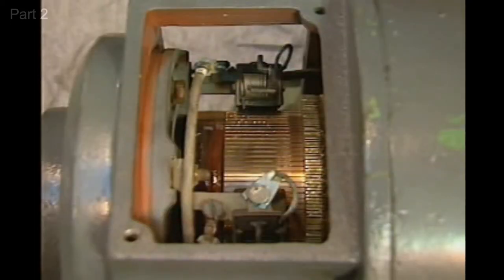Care must be taken to avoid removing this film as the commutator is being cleaned. If the film is removed, commutator efficiency will decrease and the brushes may wear more rapidly.